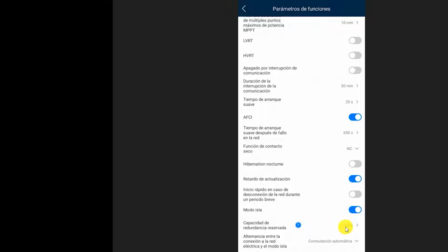We can also configure the maximum discharge of the battery. In this case we leave a 20% margin, as we always want a reserve in the battery in case we lose connection with the network, and also to extend the battery's life. We leave automatic switching enabled so that when we lose grid connection, we can switch to standalone mode.